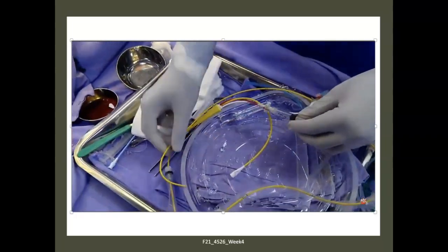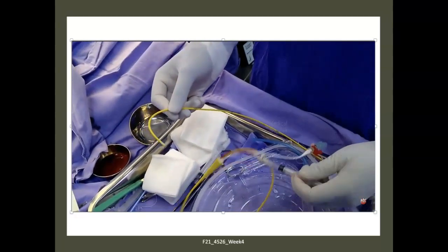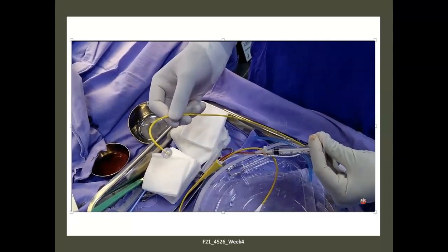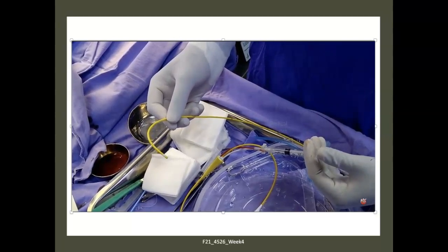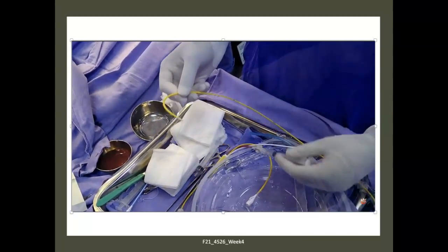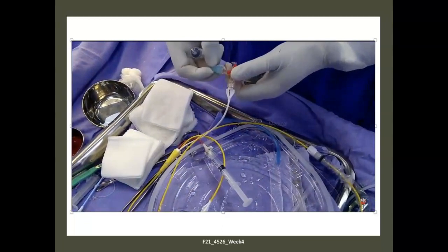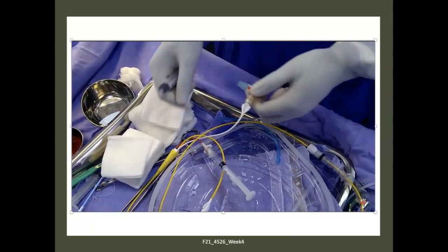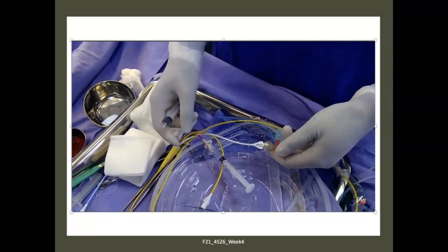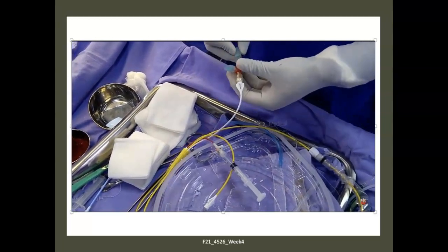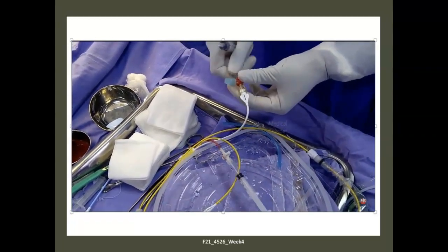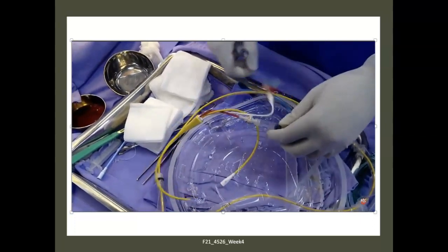The balloon of the catheter is checked by inflating 1.5 ml of air using the syringe as shown. The balloon is used to guide the catheter into the pulmonary artery by the balloon flotation technique. The balloon is also used to wedge the pulmonary artery to measure the pulmonary capillary wedge pressure, which is an indirect measurement of left atrial pressure.